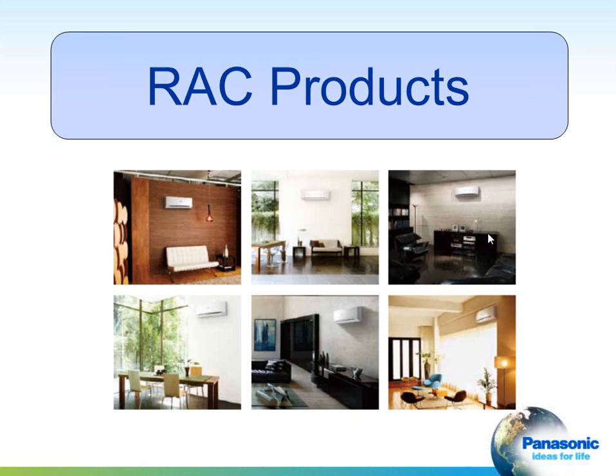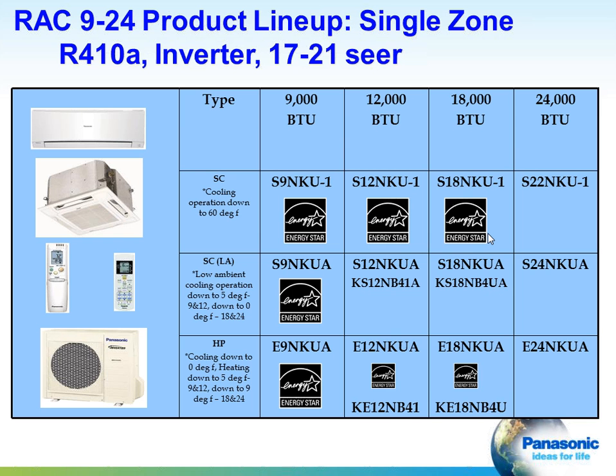Let's talk about the room air conditioning products, or the RAC products. As you can see, many applications, the in-wall units, these are high walls that we see here, an unobtrusive, fairly attractive looking product, and you can put it anywhere in an unobtrusive spot. It's up to you. The RAC product line, we'll talk about the 9,000 through 24,000 BTU product in the single zone. All this equipment is R410A. It's all inverter compressors, and the SEER ranges from 17 to 21.